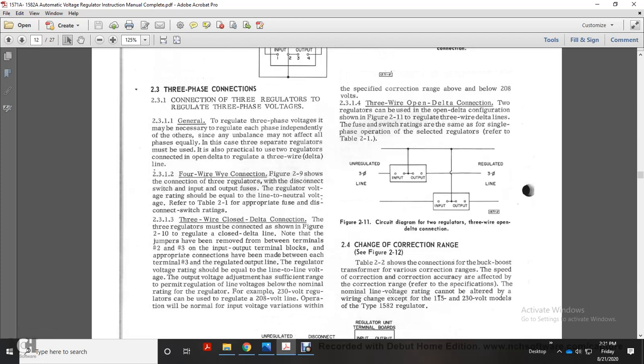2.3.1.4, the 3-wire open delta connection. 2 regulators can be used with the open delta configuration. In this Figure 2.11, the use of the regulators on 3-wire delta lines. The fuse switch is the same as in the single-phase operation of the selected regulators. Refer to Table 2.1. Figure 2.11, the circuit diagram: 2 regulators with the 3-wire open delta connections. Unregulated 3-line. The input-output regulated line, number 3, and input-output.